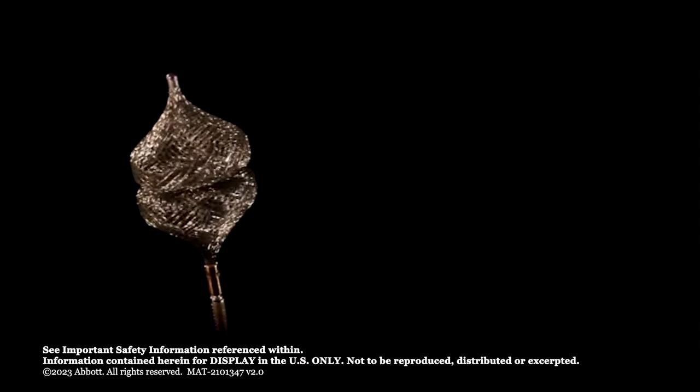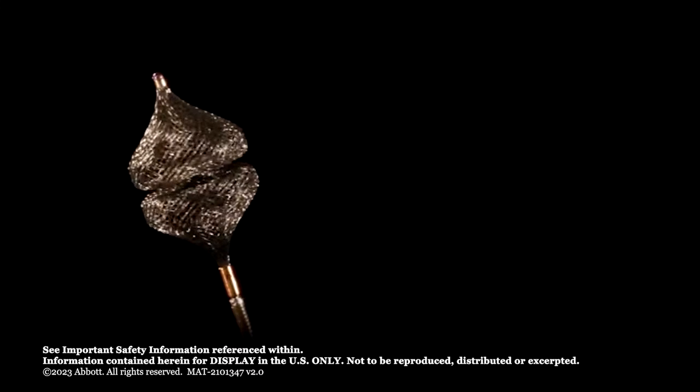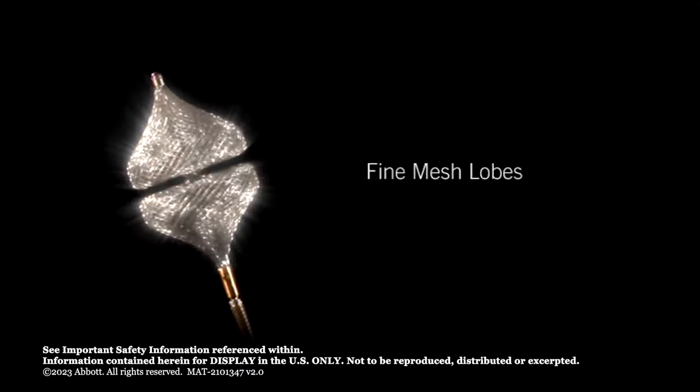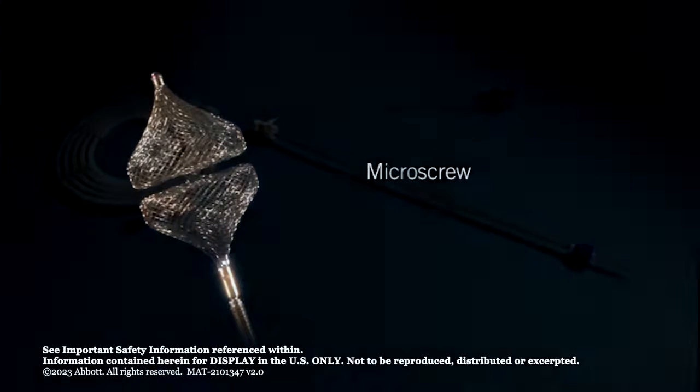The Amplatzer Vascular Plug 4 is a self-expanding nitinol mesh occlusion device consisting of two fine mesh tapered lobes. The radiopaque markers are located at the proximal and distal ends of the device. A micro-screw attachment at the proximal end of the AVP-4 attaches to a nitinol delivery wire for delivery and release.